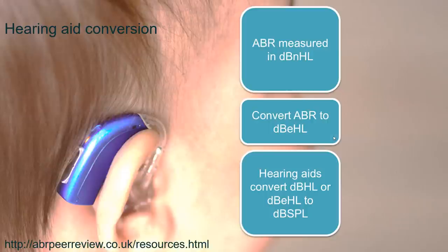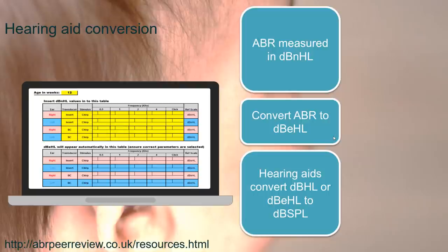In the past, converting to dB-EHL was a long-winded process requiring a stimulus correction and an age correction to be added together. Today, the conversion is much easier thanks to a dB-NHL to dB-EHL calculator in Excel developed by UK audiologist Adam Chowl, freely accessible online. All you need to do is download the calculator, input the values from your clear responses at threshold, and the dB-EHL values will be generated. This is a really nice tool and I really encourage you to download it, as it will make your lives much easier.